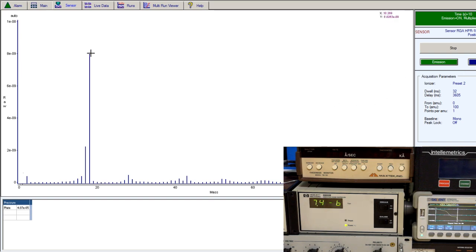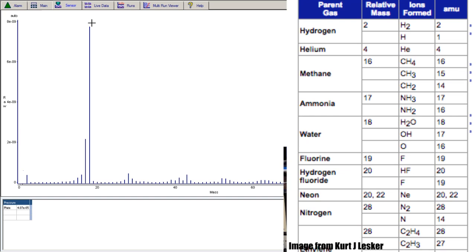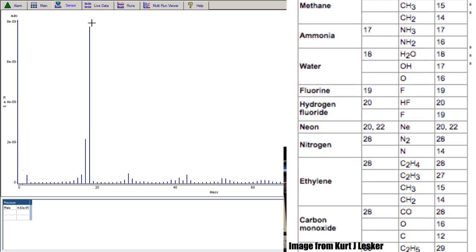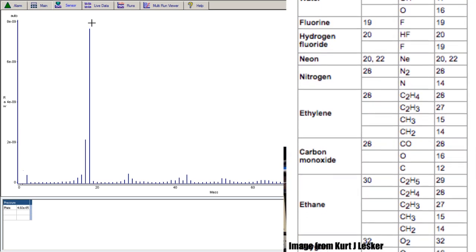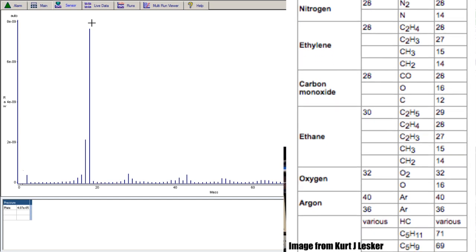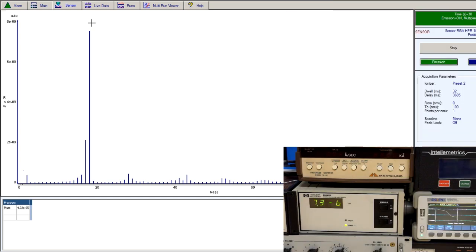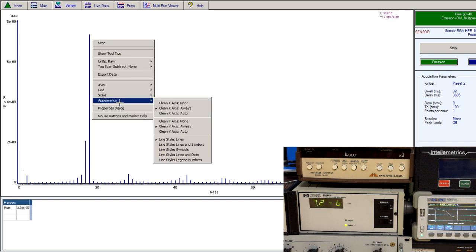Really easy to see right off the bat: at 18 AMU we have a huge spike — that's obviously water vapor. I recently had the chamber open for a while for maintenance, adding some evaporation equipment, so a lot of water has been incorporated into the chamber walls and the partial pressure of that is very high. The goal of baking out the chamber is to reduce this water so all you have left are things like hydrogen, helium, and nitrogen — that's all you really want left over.